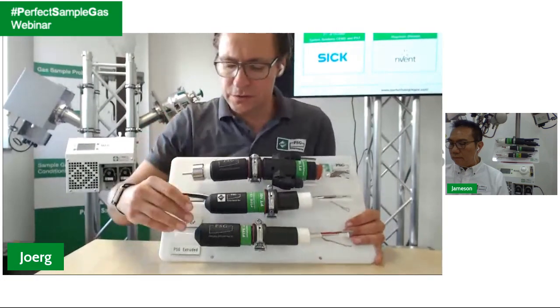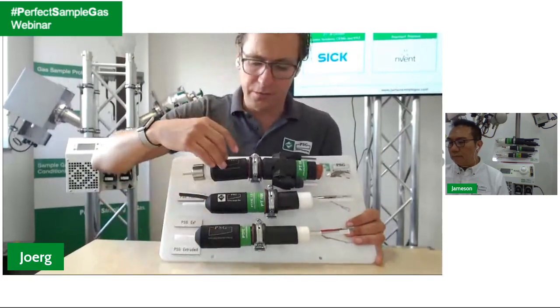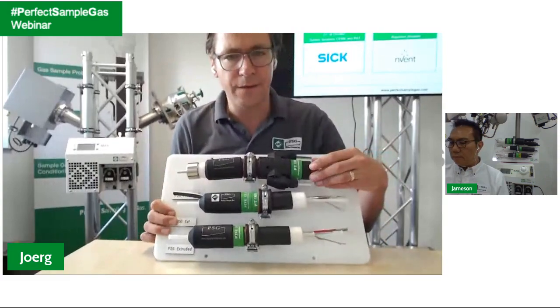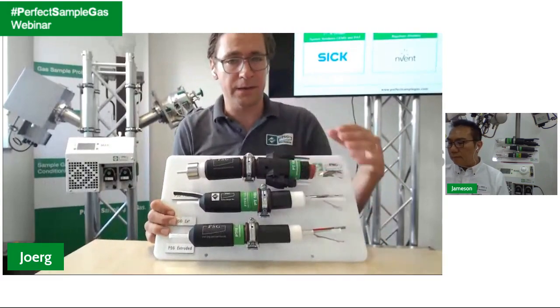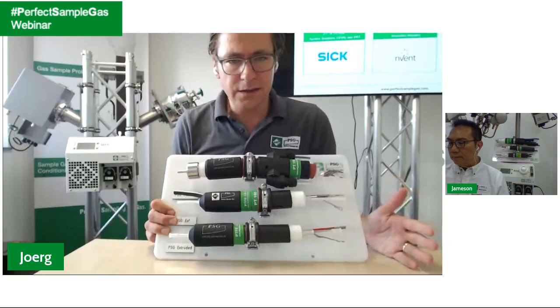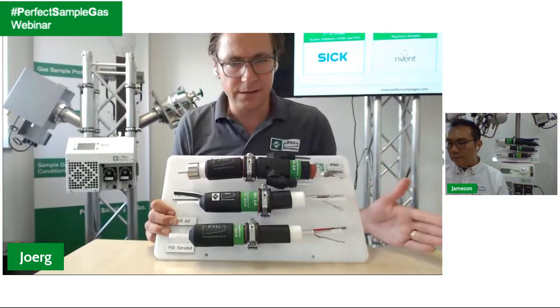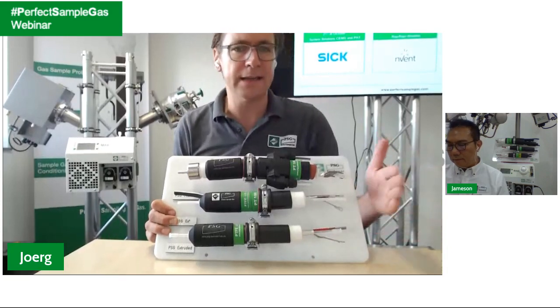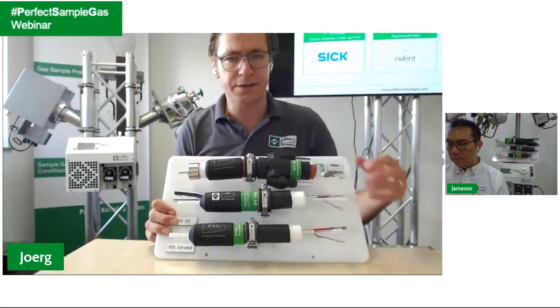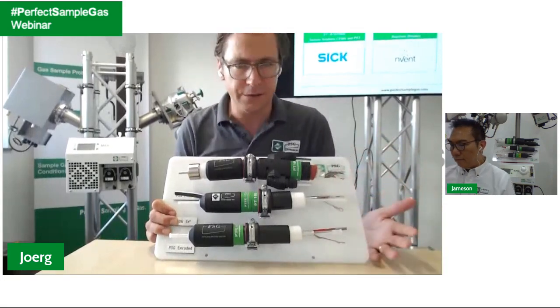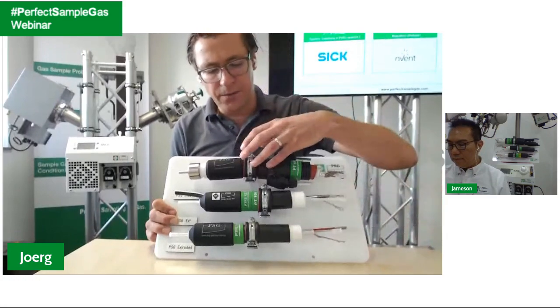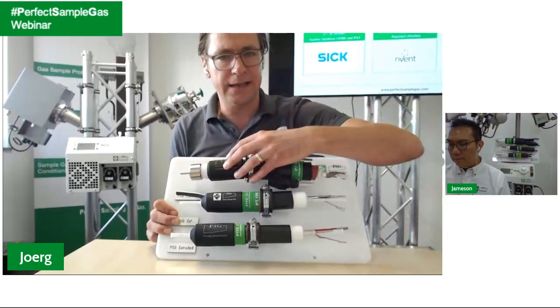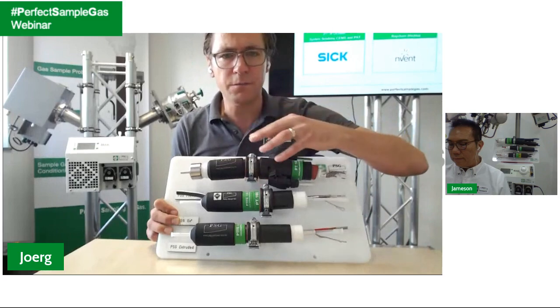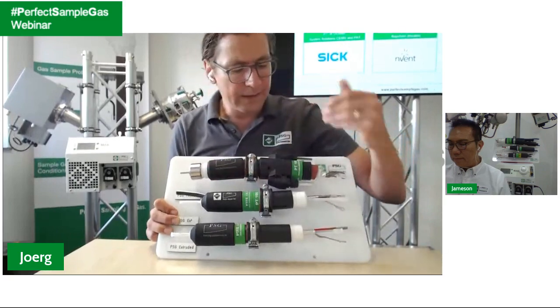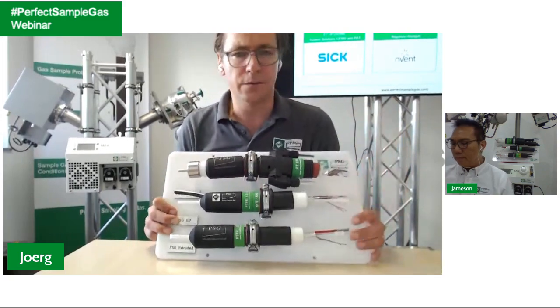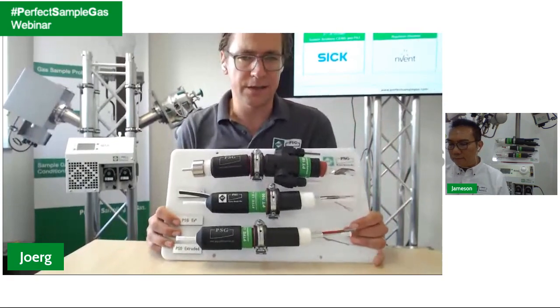Also, when you do the installation, sometimes we prefabricate these type of lines. Sometimes the line is finished, the sampling probe side and the analyzer side completely finished, so the line you receive is ready to use. Sometimes we configure just one side and the other side can be finished on site, but you have to make sure that you follow the installation instructions really closely.